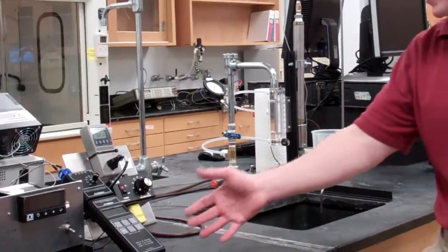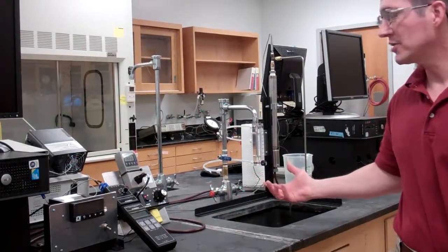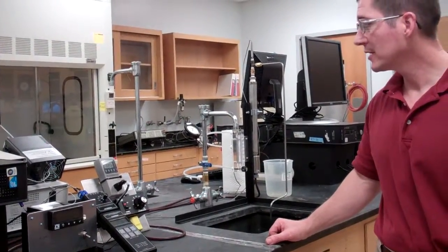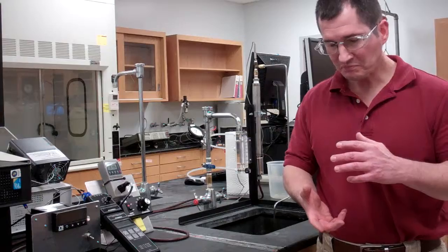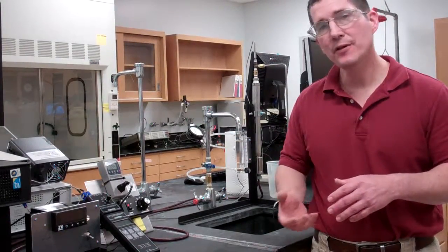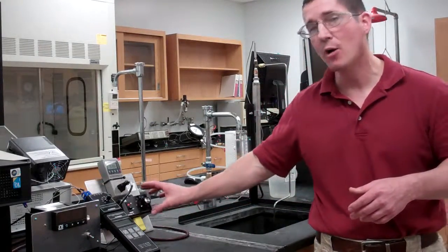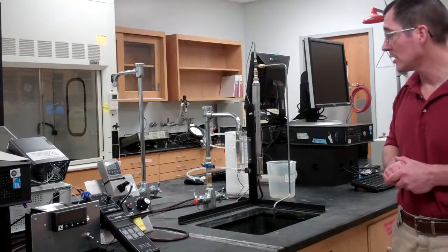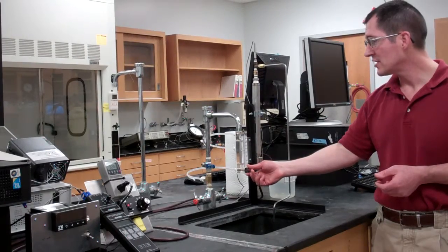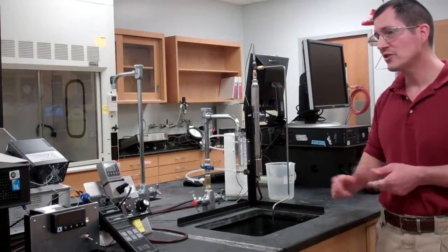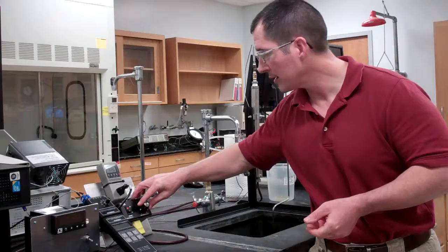You have a thermometer that measures the input temperature, and at different power settings, you'll see how much it actually changes the temperature of the device. That's going to be important, like I said, for calculating the gain of the final control element, and that's needed to program the controller so it can make a control decision about how much power to send to your final control element to change the temperature. You can do it for various flow rates. You can't change the inlet temperature, but you can change the flow rates and see how that affects the performance of your final control element. You can also try different power settings.